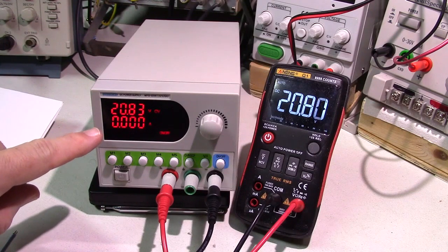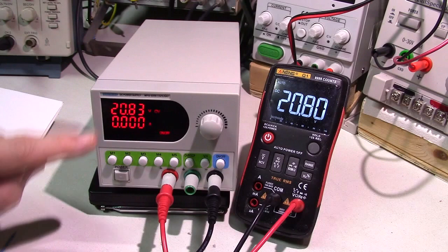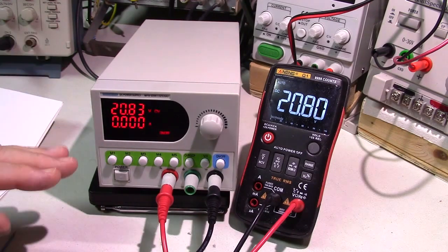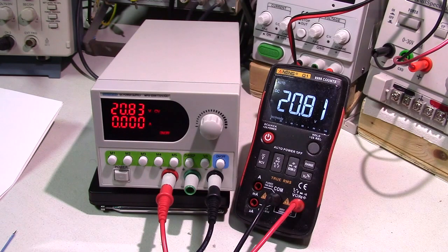You notice what happens—it goes to zero because there's nothing connected. There's no load. If you had a load, that would change and show you the current at that given voltage. You can see it's very accurate, spot-on voltage, because they calibrate it at the factory.